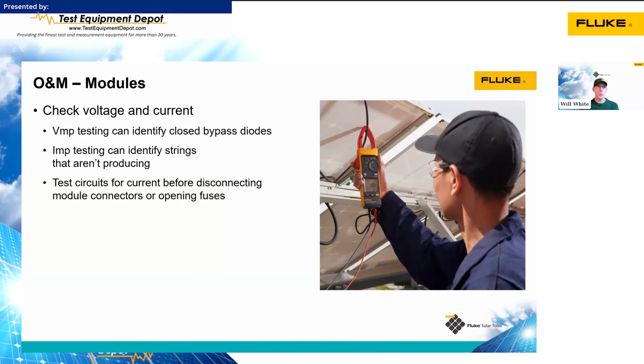So we've shut the system down. We want to open up a non-disconnect rated, non-load break rated disconnecting device, something like a fuse holder or like an MC4 connector between modules. If you open those up under load, it's going to damage the terminal. It's going to cause a safety hazard to the technician, and it could, if it's in a combiner box, potentially cause a catastrophic failure with your equipment.